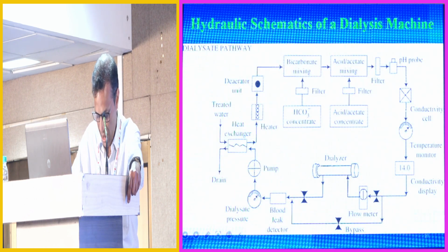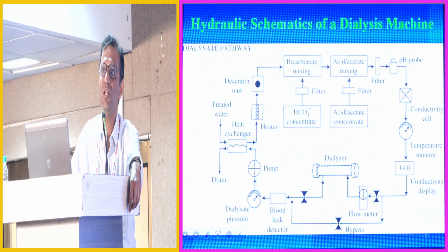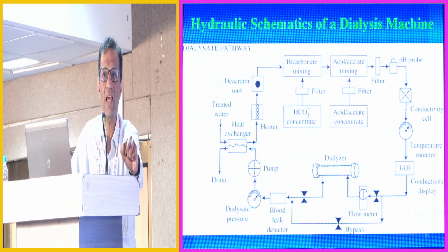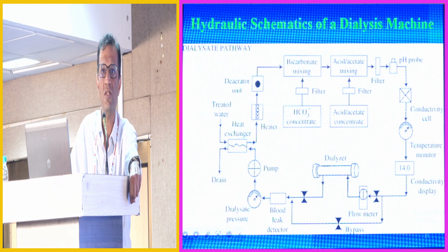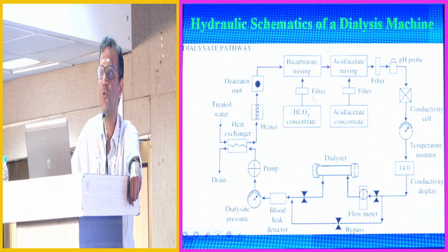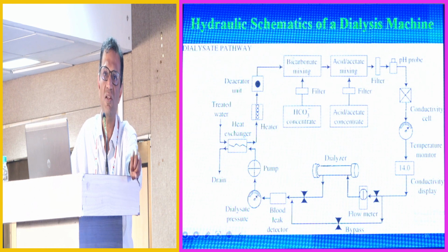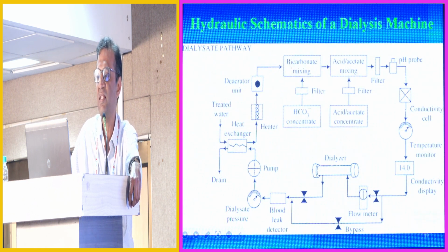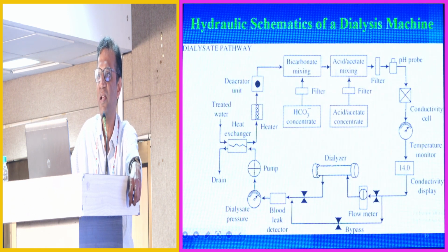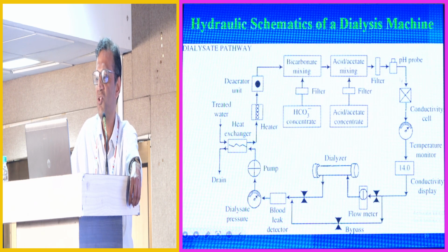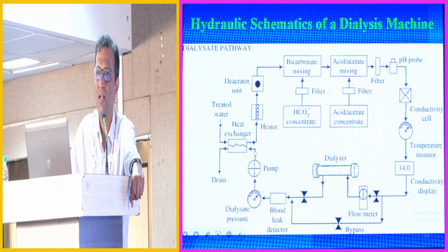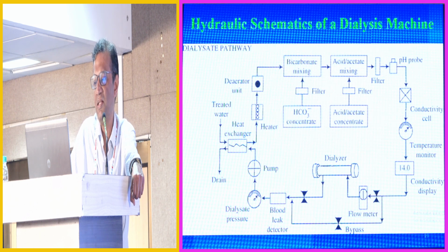Let's look at what happens inside the machine. The machine needs to take in our treated water. It needs to heat it, de-aerate it, remove air bubbles which could cause a problem, and it needs to mix it with the acid concentrate which contains most of the electrolytes and the bicarbonate concentrate, deliver it to the dialyzer, check its composition, make sure that it's delivering the right thing.